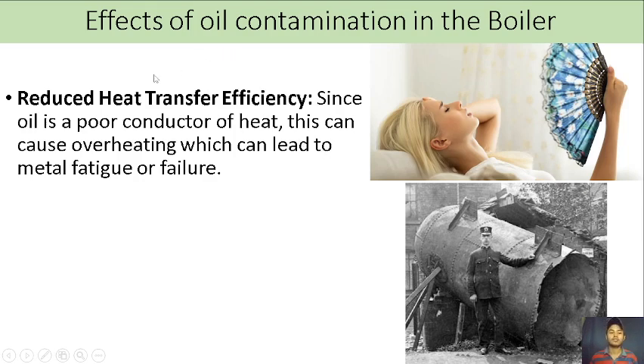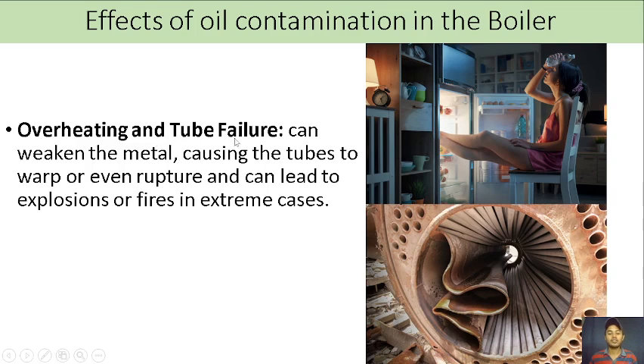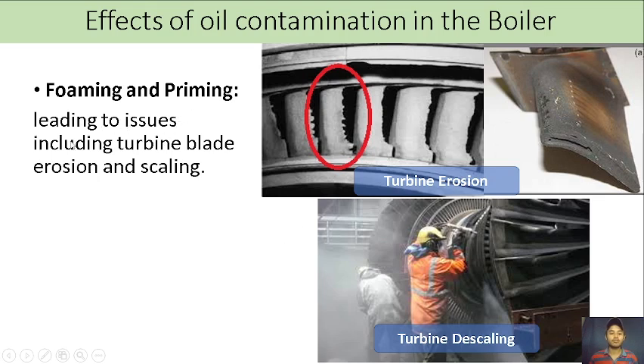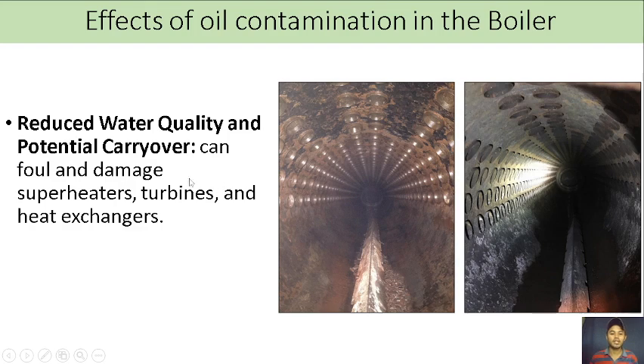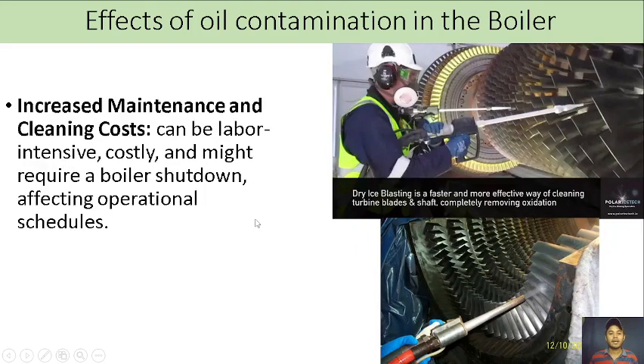So effects of oil contamination in the boiler. We have reduced heat transfer efficiency. Since oil is a poor conductor of heat, this can cause overheating, which can lead to metal fatigue or failure of the boiler. Next, overheating and tube failure. It can weaken the metal, causing the tubes to warp or even rupture and lead to explosions or fires in extreme cases. Foaming and priming lead to issues including turbine blade erosion and scaling, so your turbine blades will be damaged. Other effects: reduced water quality and potential carryover can foul and damage superheaters, turbines, and heat exchangers. And increased maintenance and cleaning costs can be labor intensive, costly, and might require a boiler shutdown, affecting operational schedules.